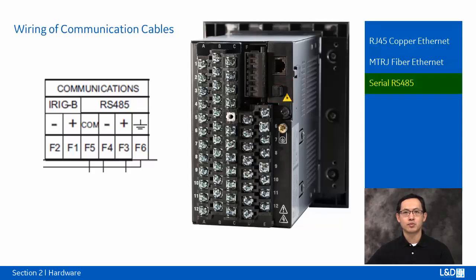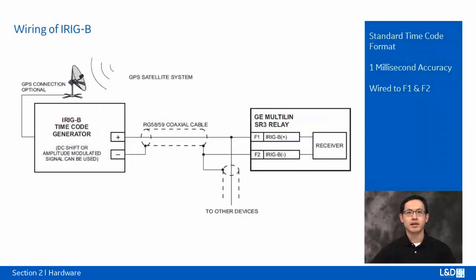The serial RS485 two-wire communication port is provided on the terminals F3 and F4, which can daisy chain up to 32 3-series IEDs. IRIG-B is a standard time code that allows time stamping of events to be synchronized among connected devices within 1 millisecond. The wiring for the IRIG-B is on the terminals F1 and F2.